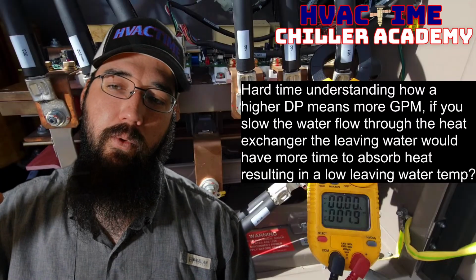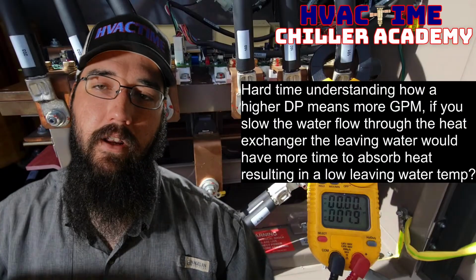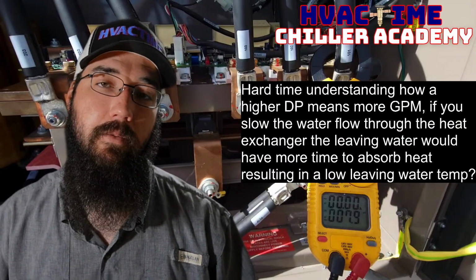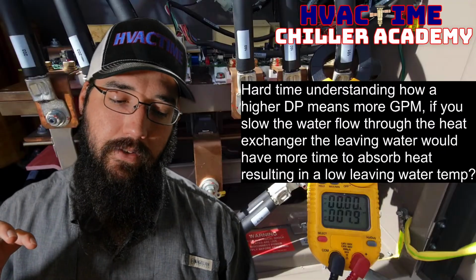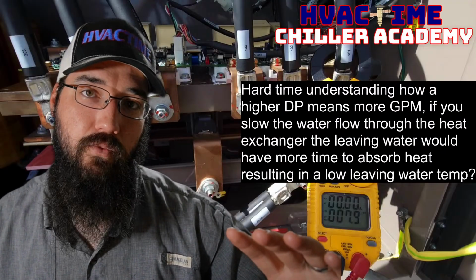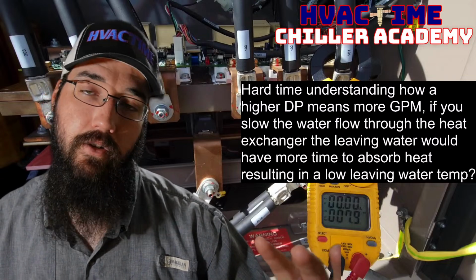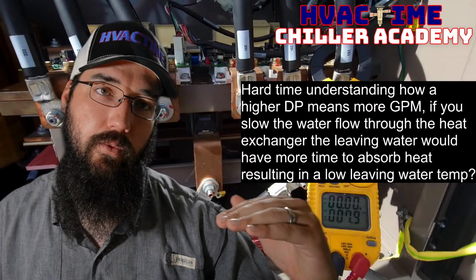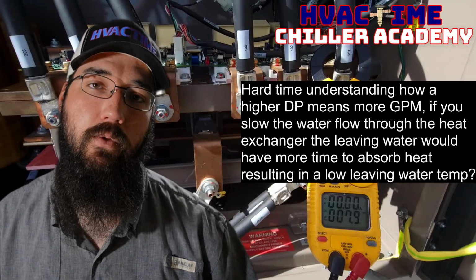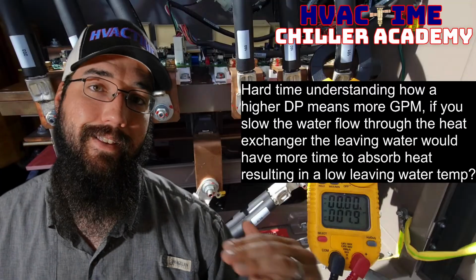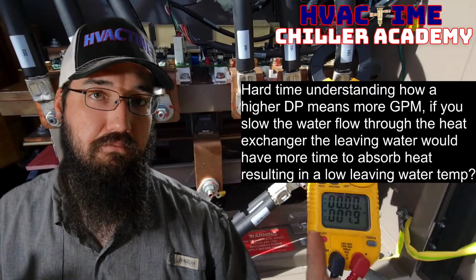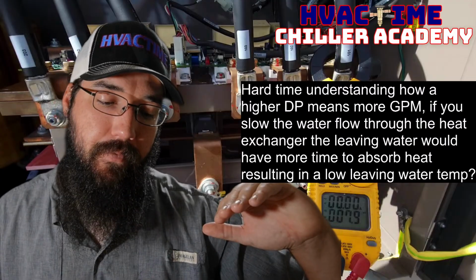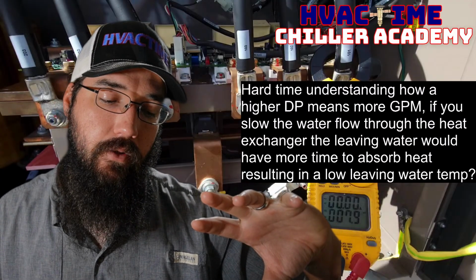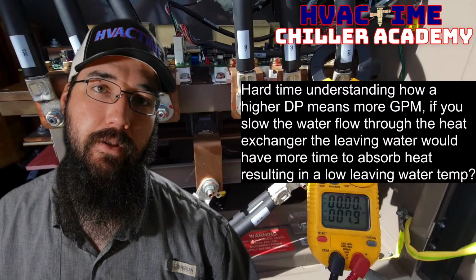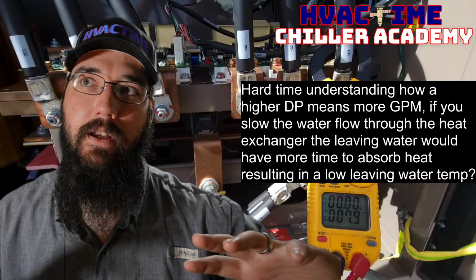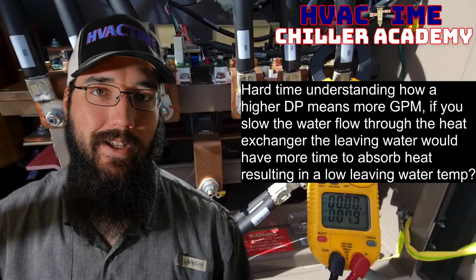So when we are running a low GPM, something we have to be mindful of is we could have a really good temperature difference, or TD, across our heat exchanger. So the entering water and leaving water, maybe we've got a 10 degree and we're at that 10 degree mark. Keep that in mind. But because we don't have enough GPM, we're not actually moving that much heat. So our chiller is not staging up that much.